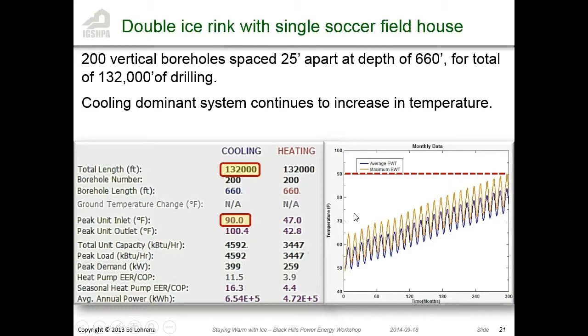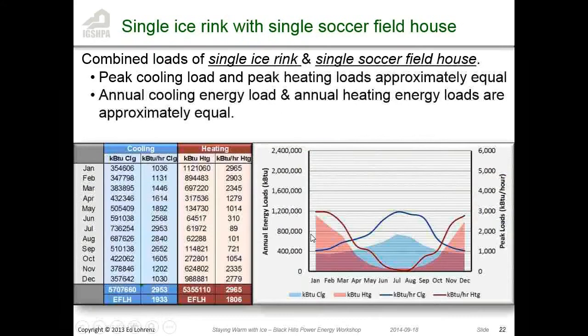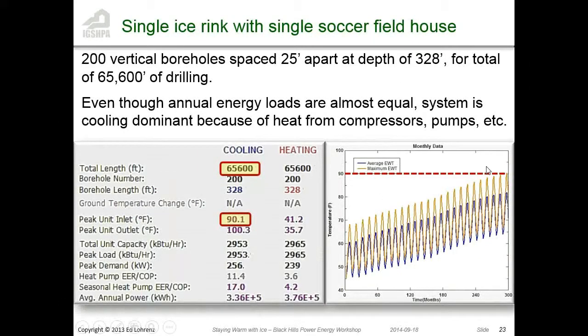So looking at a single sheet of ice versus a soccer field house, loads are a lot closer together. Peak loads are still approximately equal, and peak cooling loads are approximately equal. You're still going to get this because your compressor heat is still going to go somewhere. But we've reduced the size of the ground loop by quite a bit.